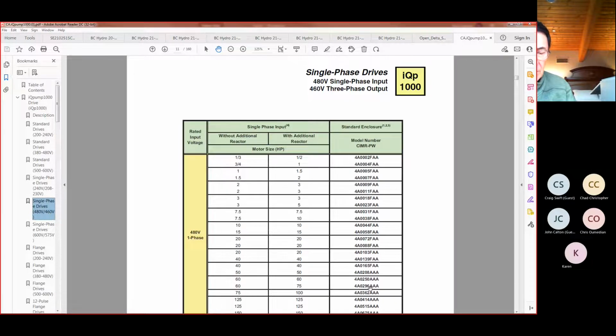Craig, correct me if I'm wrong, but the diodes are a little bit hardier. And when the capacitors go, unfortunately, we do not have capacitor thermal sensors. The tops of the capacitors will heat up quickly in a single phase situation where the DC bus ripple is extreme compared to a 3-phase input. And because capacitors are voltage shock absorbers, we're basically running them over a really rough road. We don't have a sensor to sense the temperature on the caps.